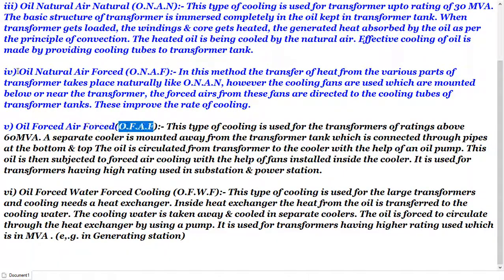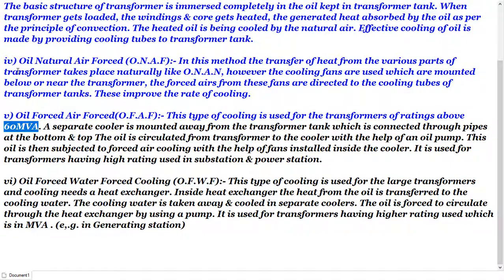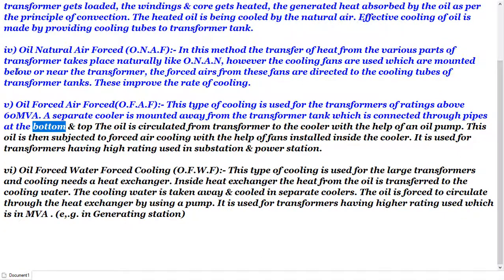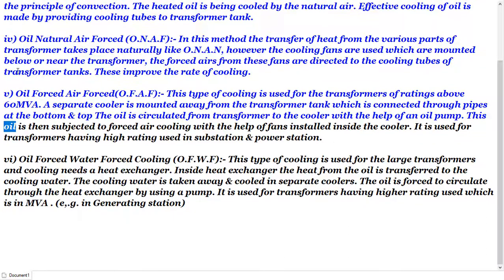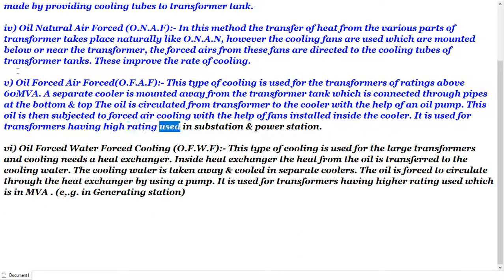5. Oil Forced Air Forced (OFAF): This type of cooling is used for transformers of ratings above 60MVA. A separate cooler is mounted away from the transformer tank, connected through pipes at the bottom and top. The oil is circulated from the transformer to the cooler with the help of an oil pump. This oil is then subjected to forced air cooling with the help of fans installed inside the cooler. It is used for transformers having high ratings used in substations and power stations.